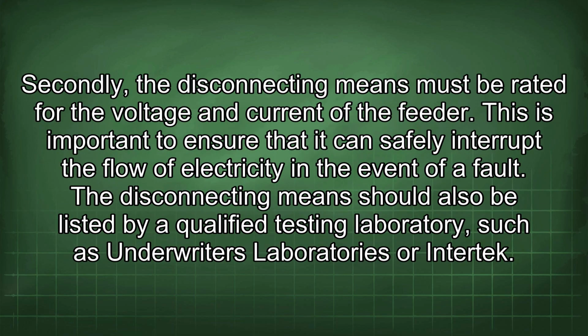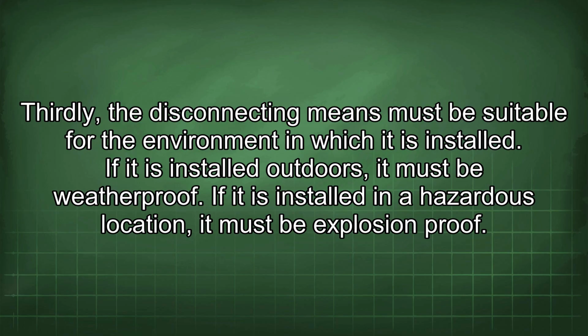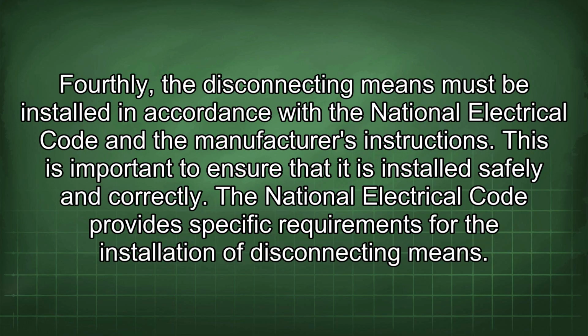Secondly, the disconnecting means must be rated for the voltage and current of the feeder. This is important to ensure that it can safely interrupt the flow of electricity in the event of a fault. The disconnecting means should also be listed by a qualified testing laboratory such as Underwriters Laboratories or Intertek. Thirdly, the disconnecting means must be suitable for the environment in which it is installed. If it is installed outdoors, it must be weatherproof. If it is installed in a hazardous location, it must be explosion-proof. Fourthly, the disconnecting means must be installed in accordance with the National Electrical Code and the manufacturer's instructions. This is important to ensure that it is installed safely and correctly.